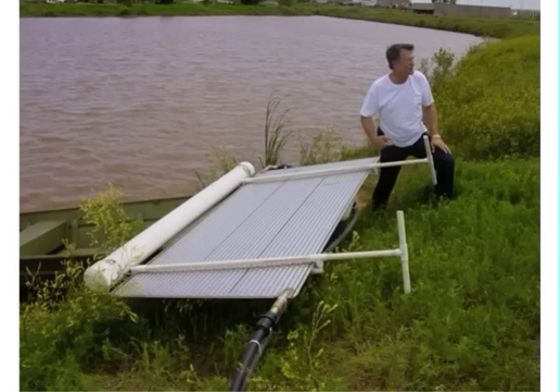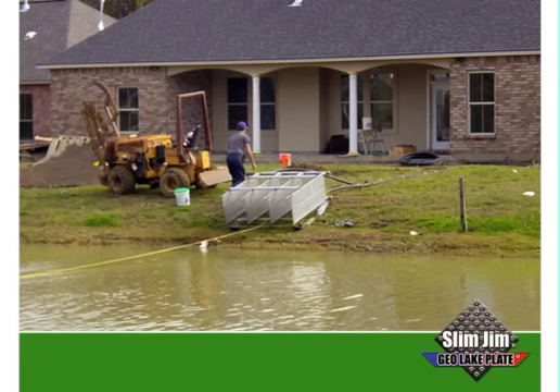Here's Alan Watts, one of the owners of AWeb Design, and one of his lake plates. Again, this one is stainless steel. You can see his float on the top to keep it vertical, and then the PVC stand to keep it up off the bottom, the supply and return pipes connected, ready to go. Here's an example of multiple lake plates manifolded. I've done a few of these myself. They put it on a little skid to drag it out into that lake bed, again making sure that you're not going to be placing into a muddy environment where it may sink and start to get into the exchange area of those plates. Because remember, you need both sides of that heat exchange lake plate so that you're conducting the BTUs you need.